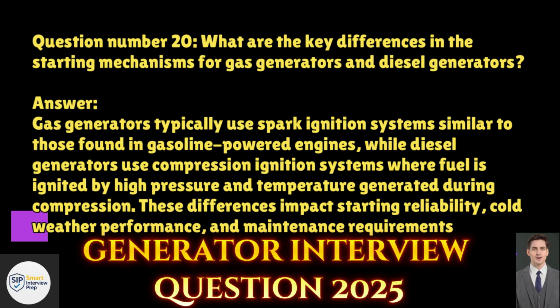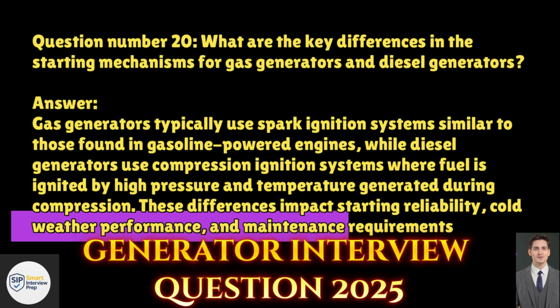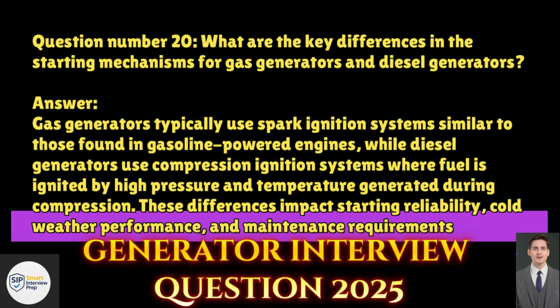Question 20: What are the key differences in the starting mechanisms for gas generators and diesel generators? Answer: Gas generators typically use spark ignition systems similar to those found in gasoline-powered engines, while diesel generators use compression ignition systems where fuel is ignited by high pressure and temperature generated during compression. These differences impact starting reliability, cold weather performance, and maintenance requirements.